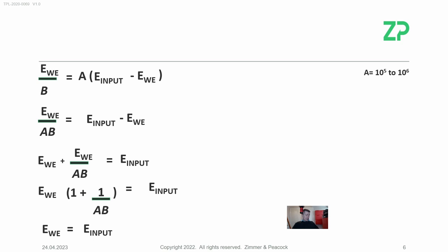Let me restate and summarize. Why do we have potentiostats? Without them, we have a two-electrode system with reproducibility problems — we lose potential between electrodes through things like electrode area, electrode fouling, and solution conductivity. Electrochemists therefore needed to measure the potential at the working electrode, so they introduced a reference electrode — that's why the three-electrode system came into place. In modern potentiostats, we use operational amplifiers as the key component at the heart of the device.